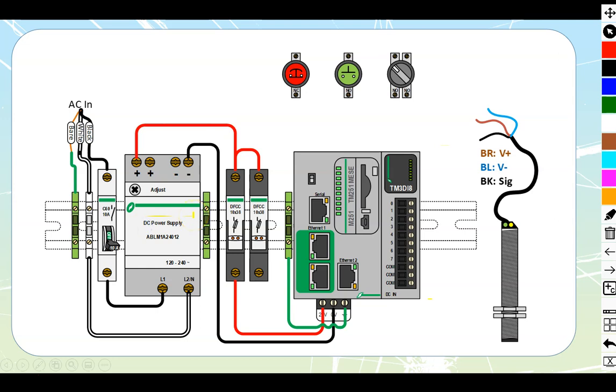Okay, so we said that we are going to work with a sinking style of input. So a sinking style of input means that we are going to have to attach our negative to the common. So the first thing that we are going to do is we are going to take a negative line out. And we're going to run that down and take that all the way out over here. And then we're going to pick up all of my common points over here. In and out, no more than two wires per terminal. It's best to use little ferrule crimps on each of these to confine your strands because you will be working with stranded wire. In most cases, I've seen people do solid as well, but stranded is always recommended. So we've got our negative carried in.